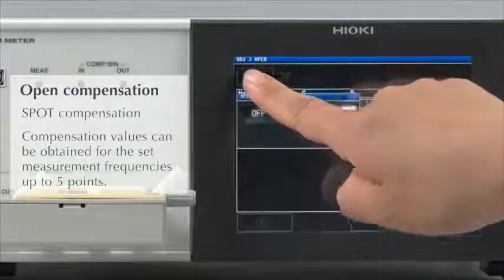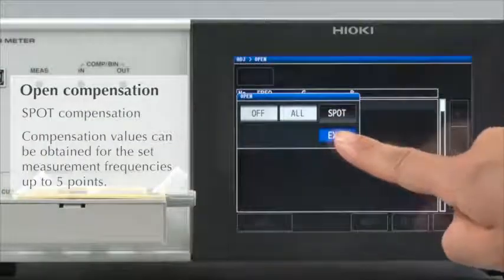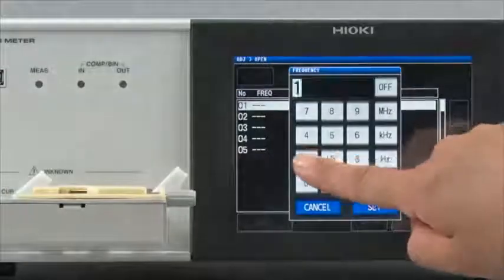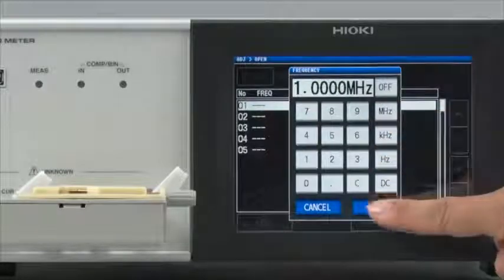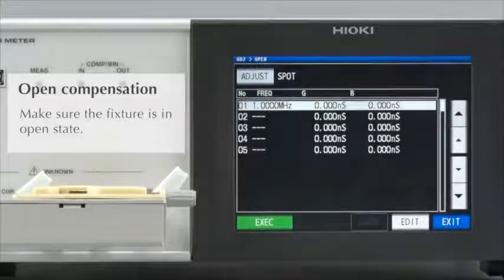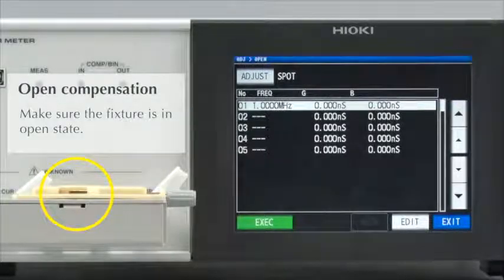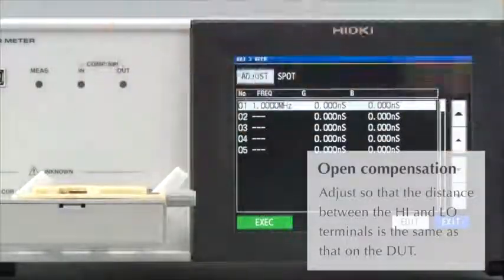Since we are only measuring at 1 MHz this time, spot compensation is sufficient. Set at 1 MHz. Adjust the fixture so that it is in open condition. Temporarily place the component being measured on the fixture.